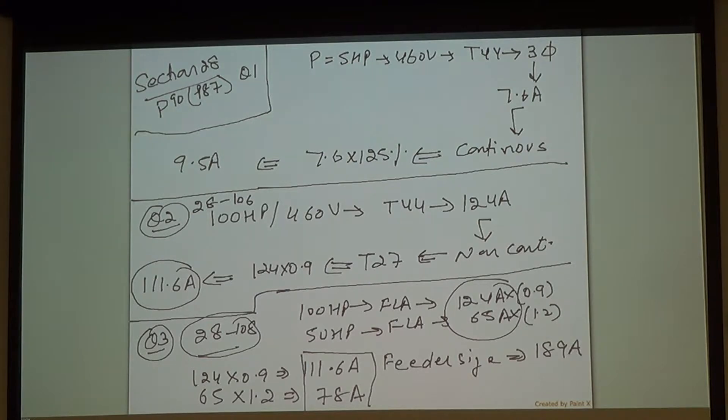When two motors, four motors, ten motors, if they're all non-continuous, you just multiply individually by their factors on table 27, and then in the end add them. That's all.